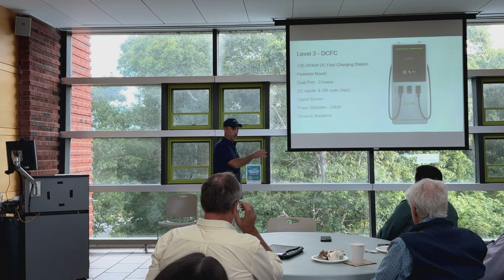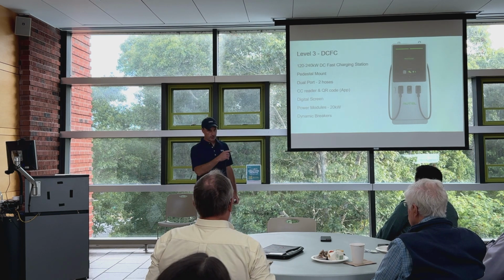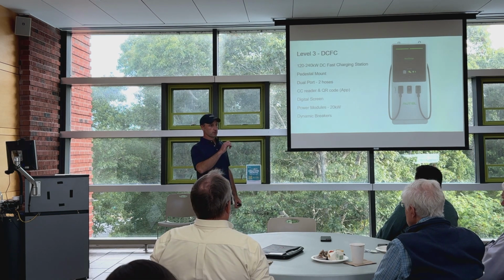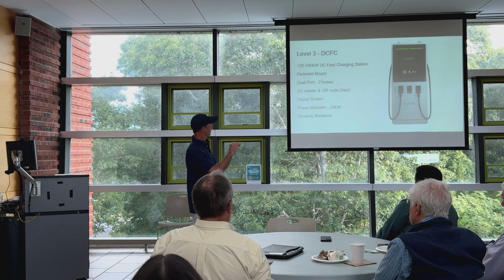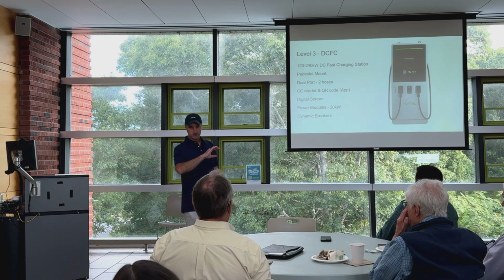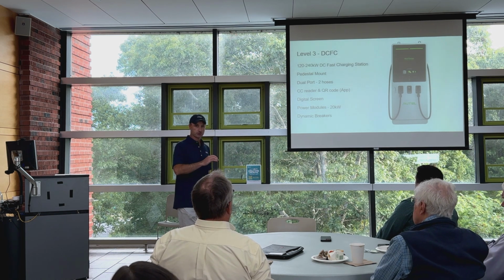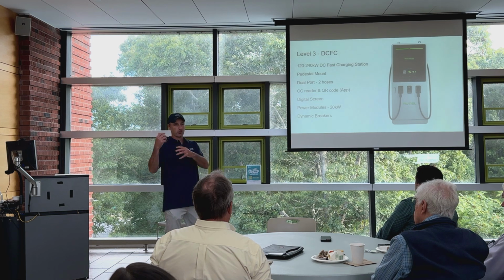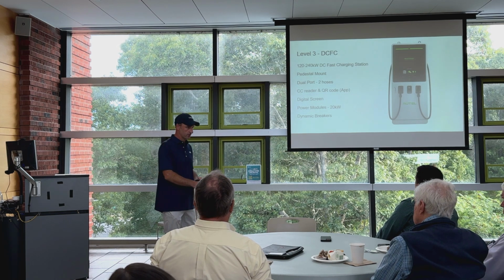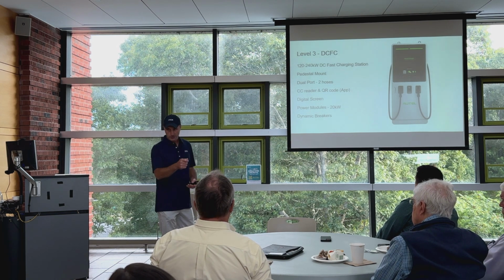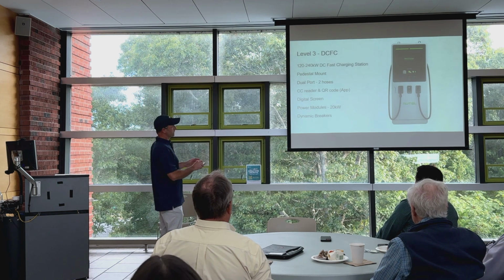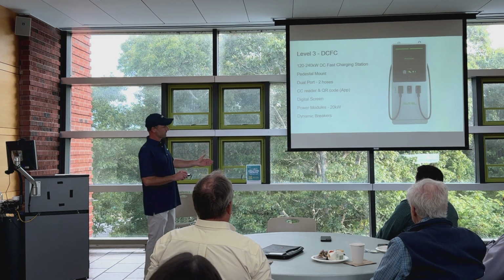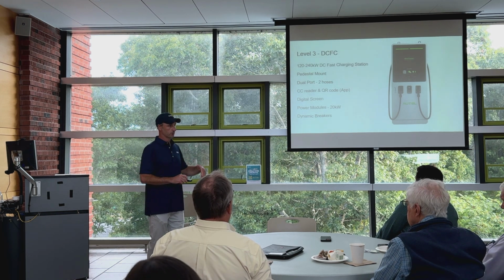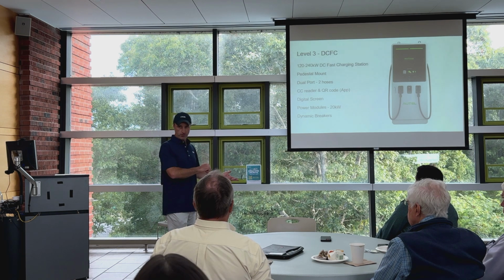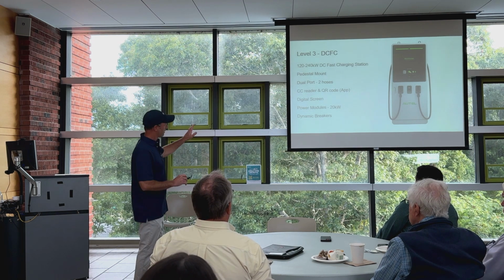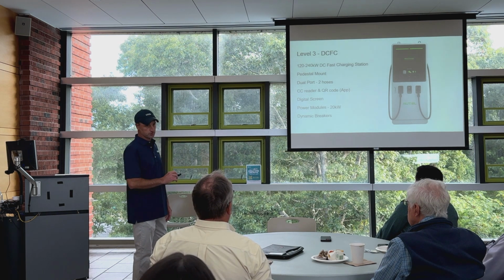This takes a 300 amp breaker in that panel box. There's a new type of ratcheting breaker called dynamic breakers that you can set to 200 amps to start, and instead of taking that breaker out and getting a 250 or 300, you can just adjust them. So we put in the below-ground wiring infrastructure with the capacity of the highest end we think we'll use, then adjust the breaker down to keep protection. These are all ground fault protected, in case the hoses drop in water.